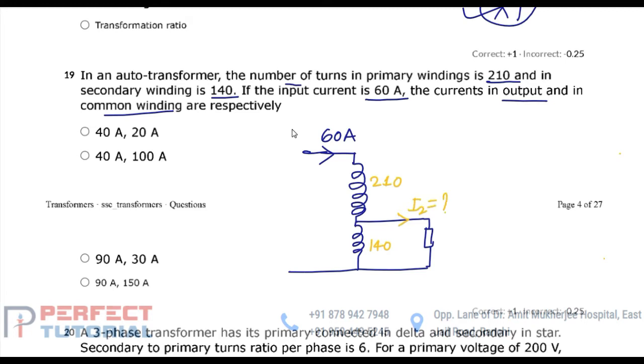The first thing you have to understand here is how the two windings, the common and uncommon windings, are connected in an auto transformer. A tapping point is provided in such a manner that the common winding and uncommon winding are connected in series additive polarity. Meaning, if this is the dotted terminal of the uncommon winding, then the undotted terminal of the uncommon winding should be connected with the dotted terminal of the common winding, so that it can satisfy Lenz law, so that the primary EMF opposes the secondary EMF. Meaning, if the current flowing through the uncommon winding is leaving the dot, then the current flowing in the common winding should enter the dot. Okay, so this should be the IC current.